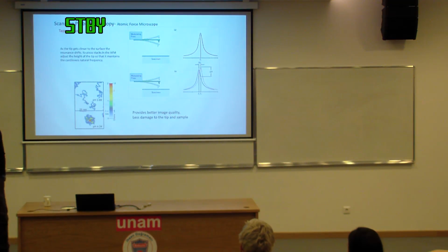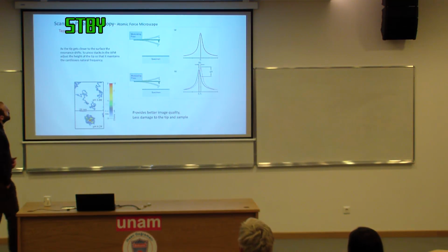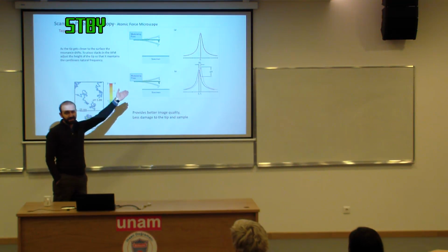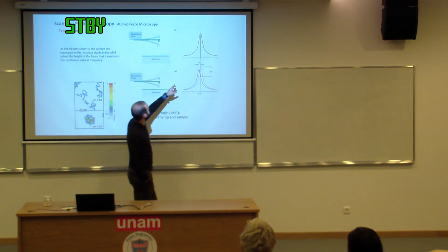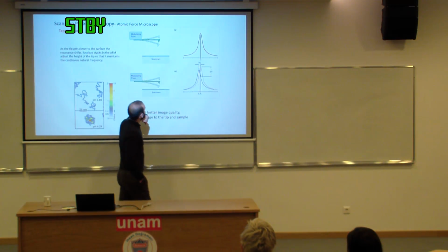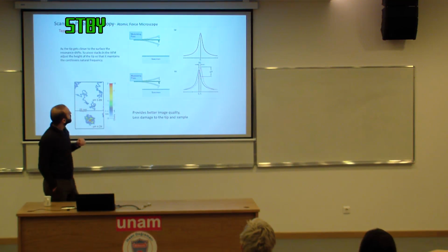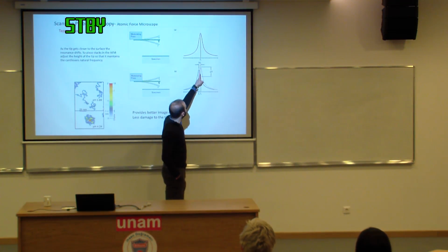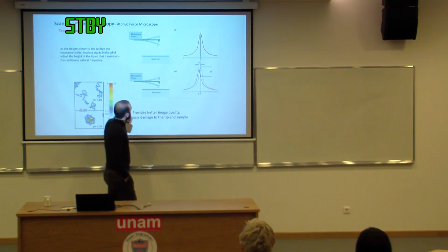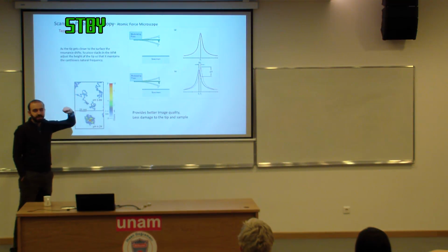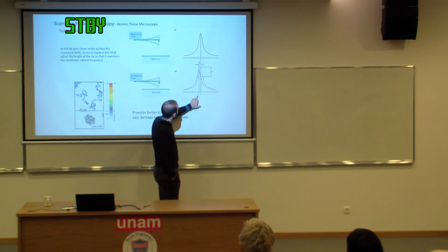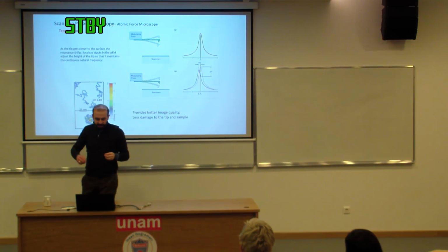Another useful mode is tapping mode. Actually, this is what you use mostly. What you do is you modulate the tip at a specific frequency. As it's a cantilever, there's a natural frequency, so there's this resonance frequency. Okay? And you drive the tip either at that frequency or slightly shifted, like somewhere around here. Okay? And what happens is, as you bring the tip close to the surface, because of the interactions, you change this natural frequency of the oscillation.